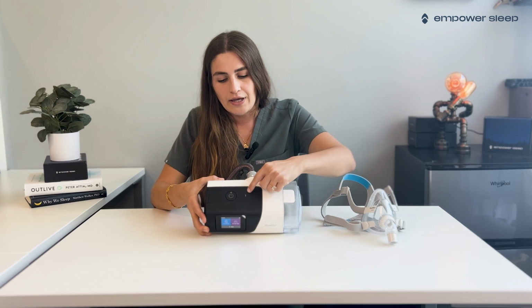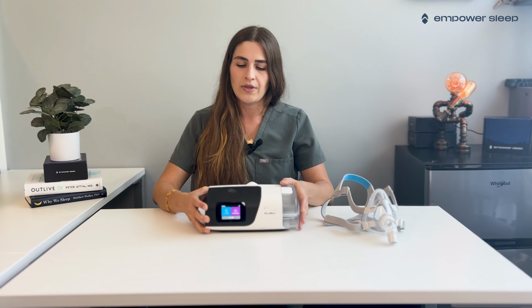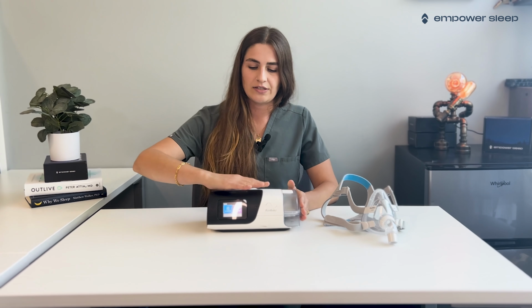Right next to the power button, we see a very tiny little rectangle here, but that's a light sensor. So with this touchscreen device, if I have my hand placed over the light sensor for an extended period of time, my screen will start to get really dark because the machine thinks that you're in a dark room. So by removing your hand after a few seconds, the light should turn back on. However, when you actually have the therapy running and active, you will notice that the machine goes completely black after a few seconds, which is normal.